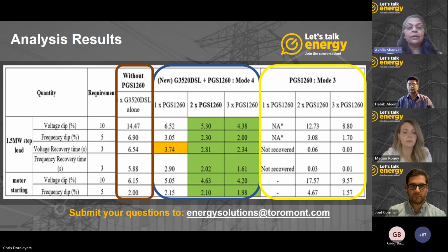The next column, highlighted in red, shows the results of the test when only the generators were subjected to the two loads, the 1.5 megawatt and the motor starting. As you can see, the voltage dip with the 2.5 megawatt gensets was around 14.4% as compared to the requirement of 10% max. Now, the same 3 units of 2.5 megawatt were subjected to the same set of loads, but in combination with a single 1260 kilowatt battery energy storage system. And these results you're seeing in the blue box.